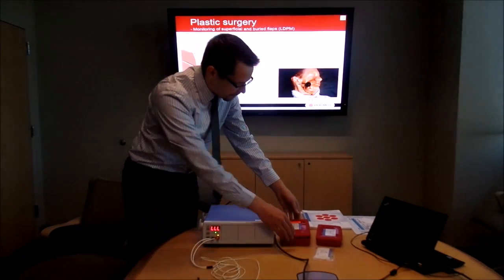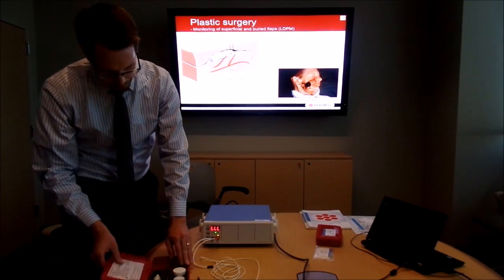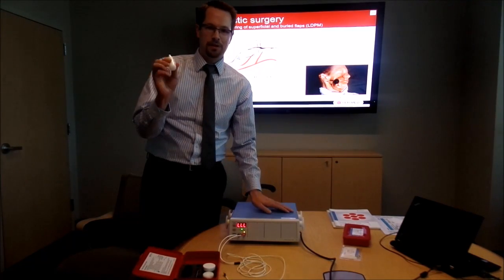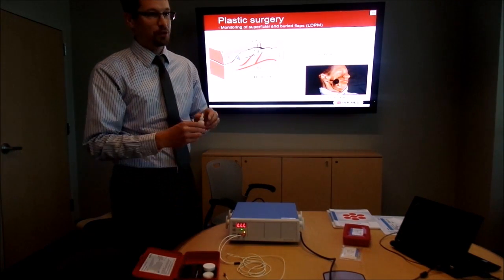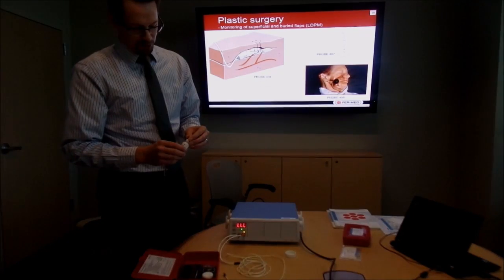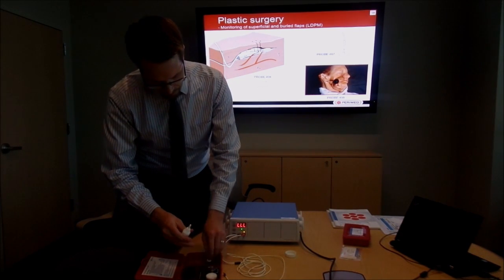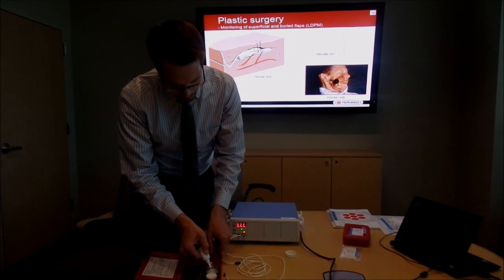For calibration, we have this calibration device. Calibration fluid, we call this motility standard. It's a suspension of small latex spheres, 0.3 microns in size. And because we can control the concentration of these latex particles, we also then know what the probe should measure as we're dipping this into the calibration solution, the motility standard. So to do this calibration, I'll empty this bottle into this little glass jar that comes in the calibration kit. If this fluid is in good shape, it should look almost like milk.